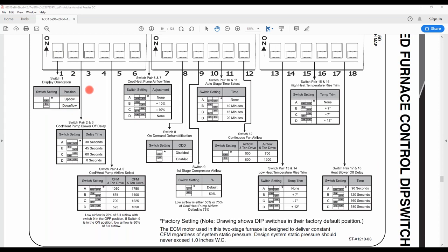Dip switch number 2 and 3, those are your cool heat pump blower off time delays. When the unit shuts off, the blower off time delay comes factory set for 30 seconds. You have the option of making it 0, 30, 45, or 60 seconds. Fairly simple, just by flipping them on. If you want 0 seconds after the unit shuts off, then you will flip number 2 and number 3 to the on position.